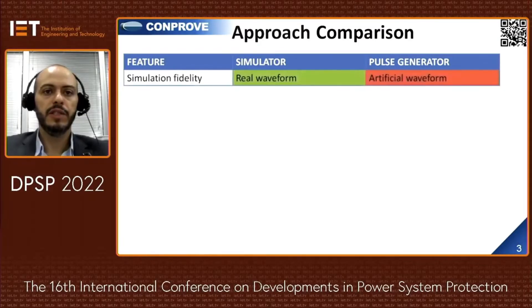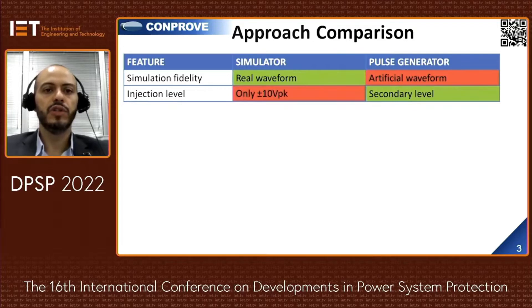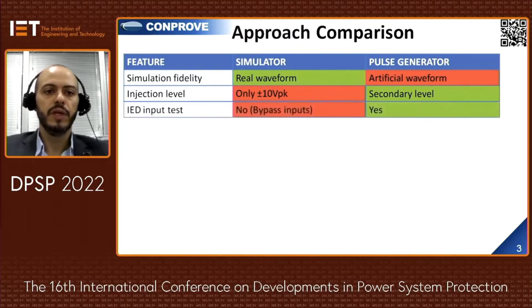About fidelity, one approach uses real waveforms created by modeling the system, and the other uses artificial pulses that do not occur in practice. The simulator only injects up to 10 volts and cannot be connected directly to the IED. On the other hand, the pulse generator uses secondary-level output for current and voltage and is linked to the input circuit of the device under test. Using the simulator, you have to bypass the input circuit; in contrast, the pulse generator technology can connect directly to the IED.